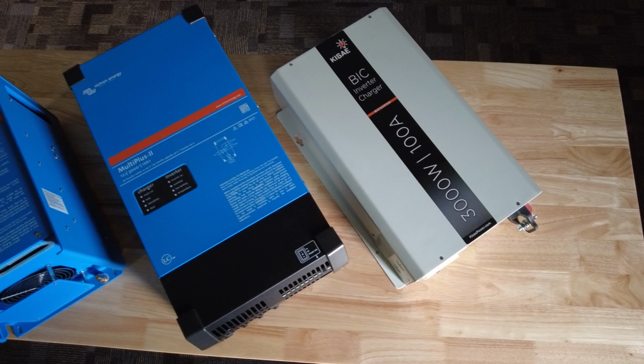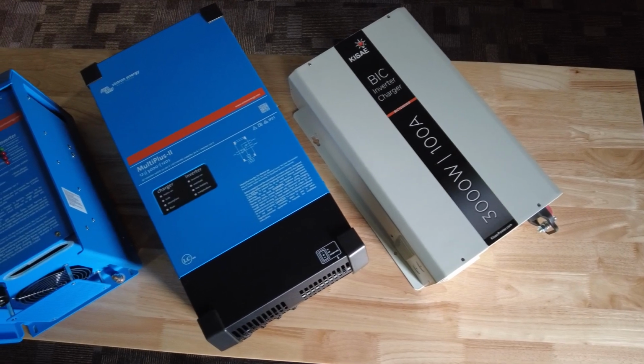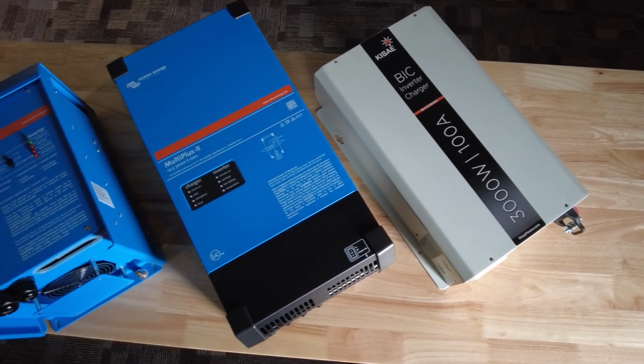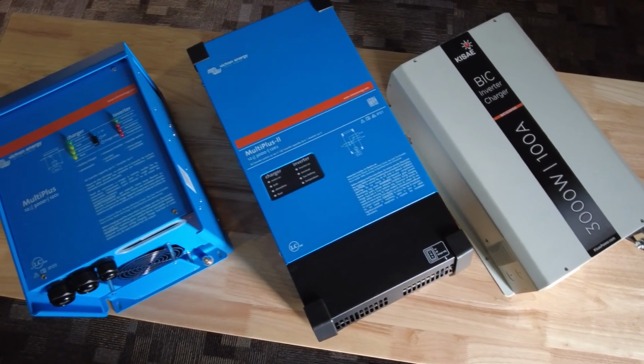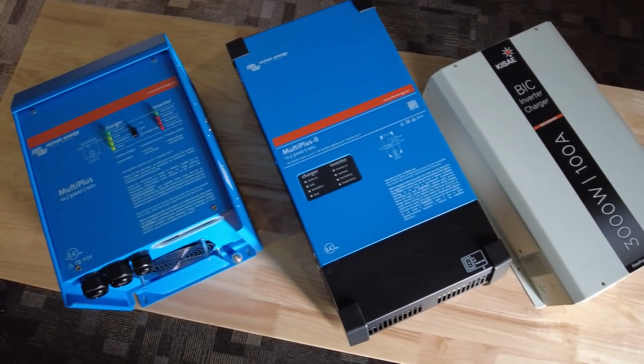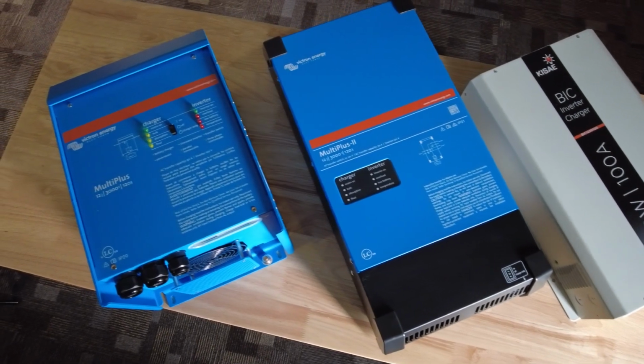The inverter charger will require an input from your battery bank using properly sized cables, fusing, and a recommended disconnect switch. The inverter charger will also require an AC input that comes from your power center shore power source. Finally, there is an AC output that will feed all the onboard AC circuits through the power center AC load bank.